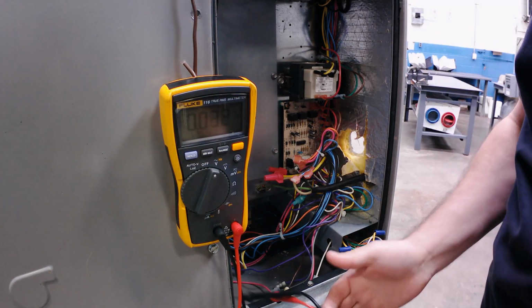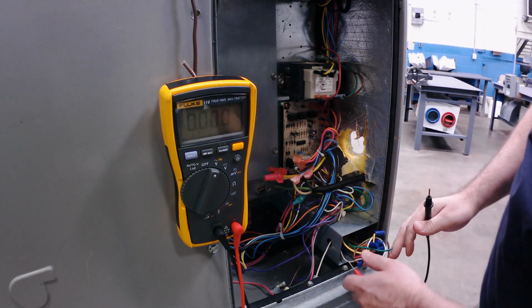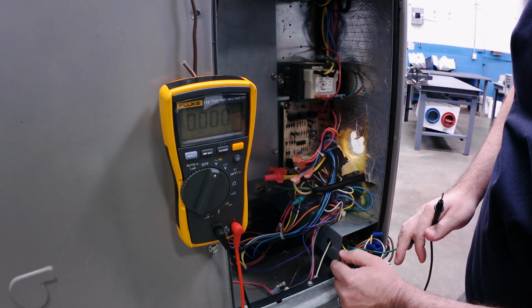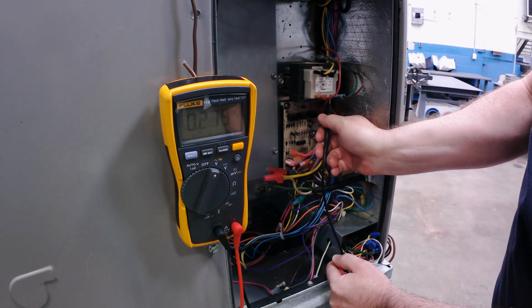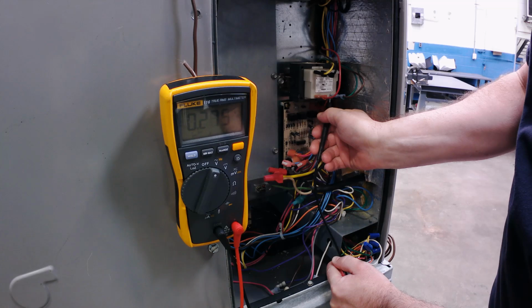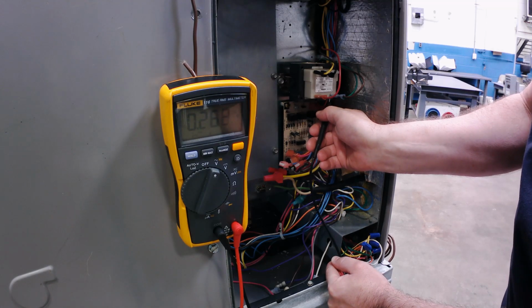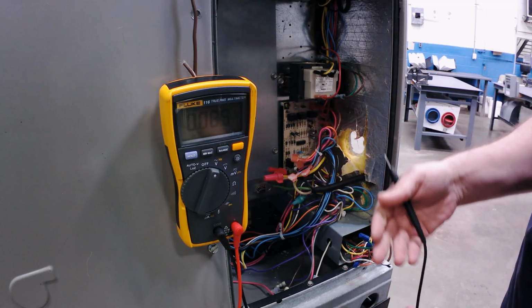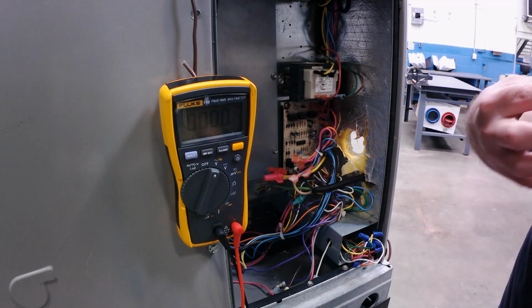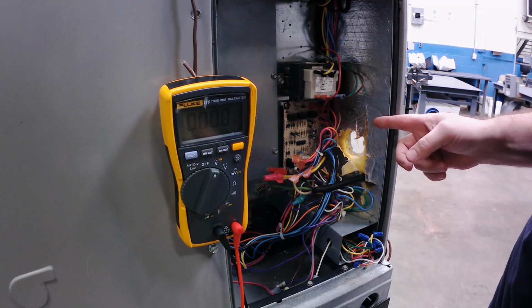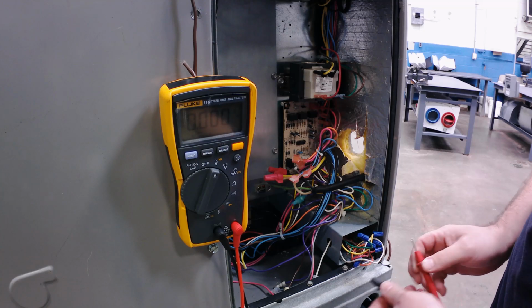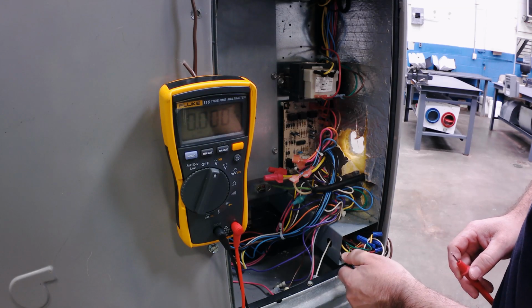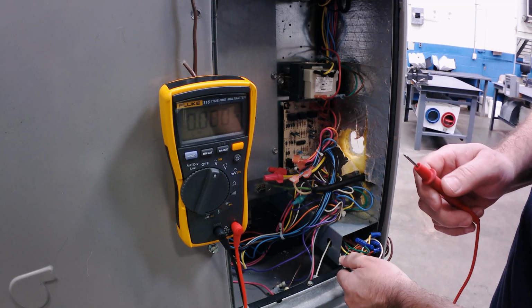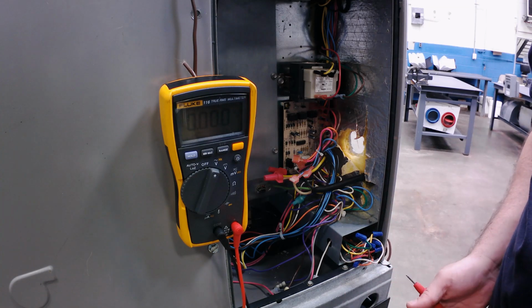So real simple, I just pulled the thermostat face off. If I were to check here and grab the common on my transformer and get something weird, 11 volts, 10 volts, 0 volts, something other than 24, I know my thermostat has to send 24 volts down G. If I don't see that, then I don't blame the thermostat yet.